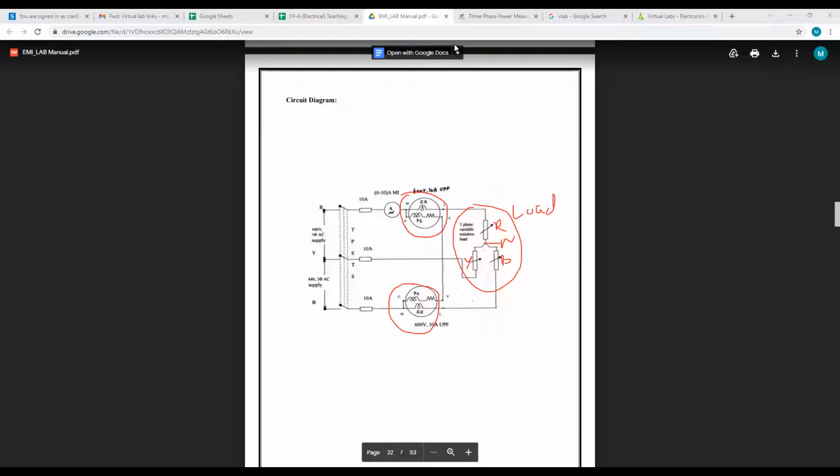For the wattmeter, already we have studied that one. Current coil and potential coil will be there inside the wattmeter. So it has 4 terminals here now: M, L, C, V. The R phase of the variac should be connected to one ammeter terminal. Next, the other ammeter terminal should be connected to the M.